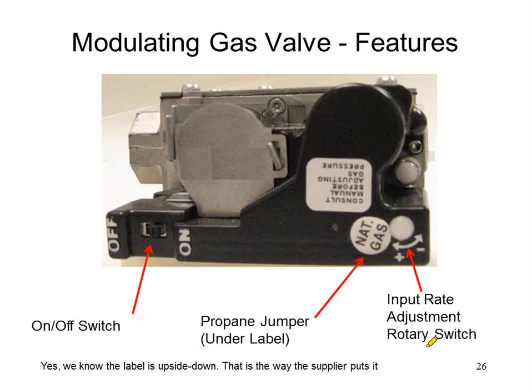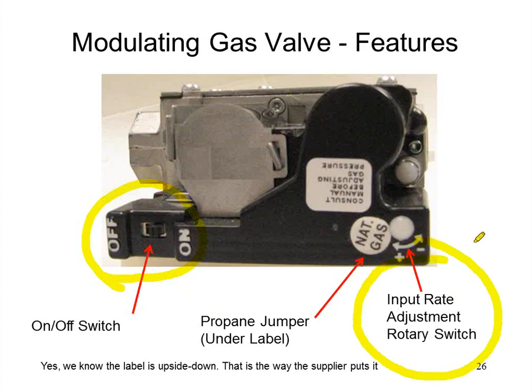The modulating gas valve itself is nothing overly sexy or exciting. It does have an on-off switch, like most gas valves do. So sometimes you might get an error on your Infinity stat saying, "Hey, make sure the gas valve is switched on," and you'll go look at the red handcock on the outside, and it's in the full flow position, and you think it's on, but there's actually a switch on the inside on the gas valve as well. There is an adjustment screw that you can utilize to set up the gas valve.